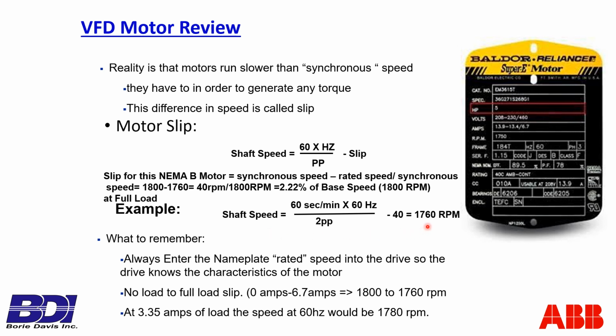And our motor here is 1760. What this means is, if you provided this motor with 460 volts and loaded it to 6.7 amps, it would be running at 1760 RPM. So that's the full load rating of the motor. That's one point where the motor's happy. Now the fact of the matter is, rarely do you see motors operate at exactly what's on the nameplate. They may be running at 460 volts, 60 hertz, but they may be only drawing 3.35 amps of load at the speed of 60 hertz. Well, that's not the nameplate.